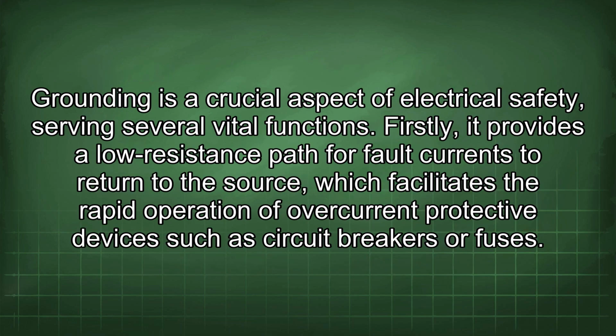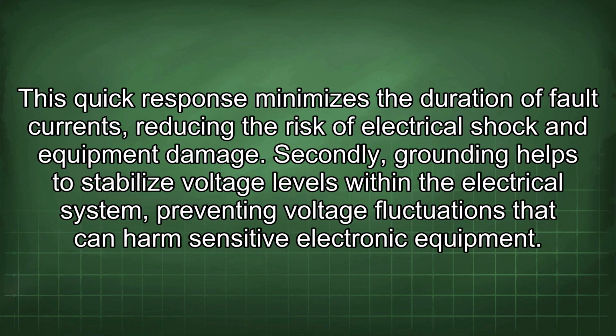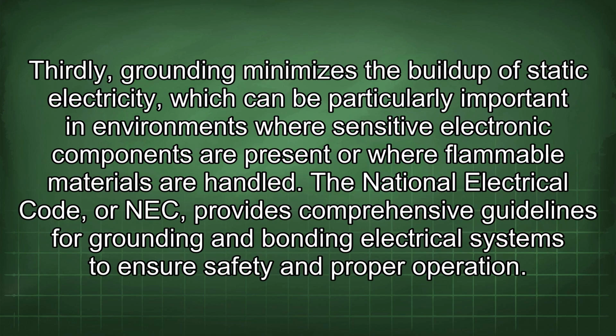Grounding is a crucial aspect of electrical safety, serving several vital functions. Firstly, it provides a low resistance path for fault currents to return to the source, which facilitates the rapid operation of overcurrent protective devices such as circuit breakers or fuses. This quick response minimizes the duration of fault currents, reducing the risk of electrical shock and equipment damage. Secondly, grounding helps to stabilize voltage levels within the electrical system, preventing voltage fluctuations that can harm sensitive electronic equipment. Thirdly, grounding minimizes the buildup of static electricity, which can be particularly important in environments where sensitive electronic components are present or where flammable materials are handled.